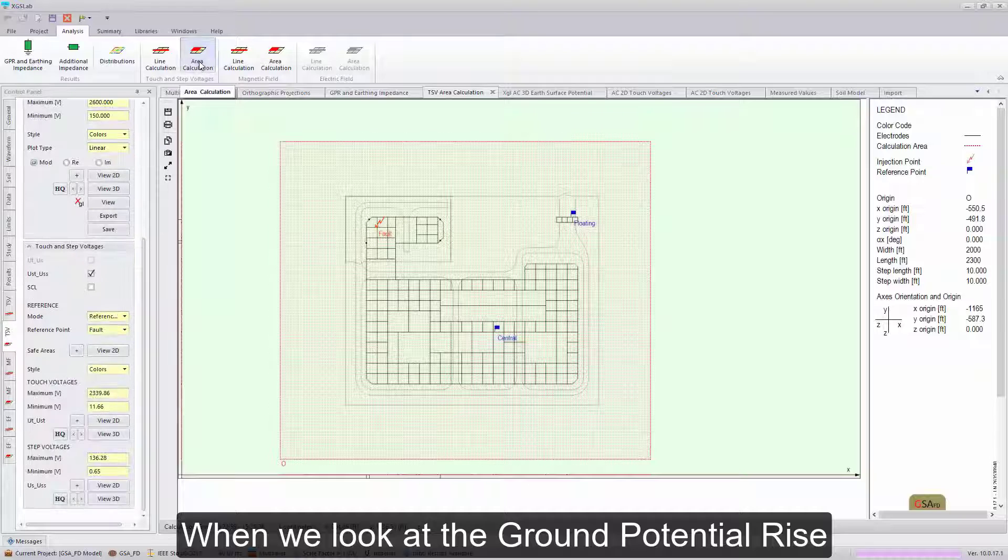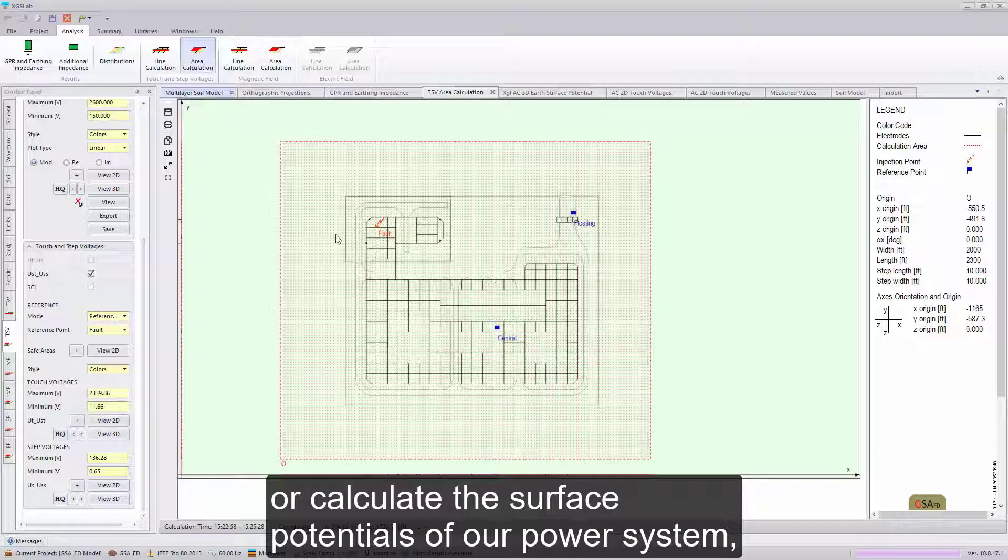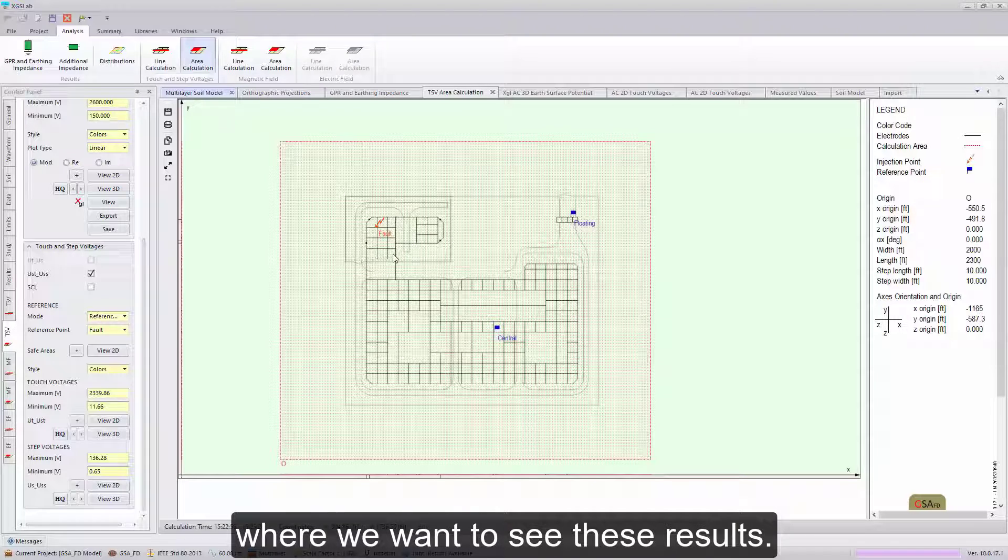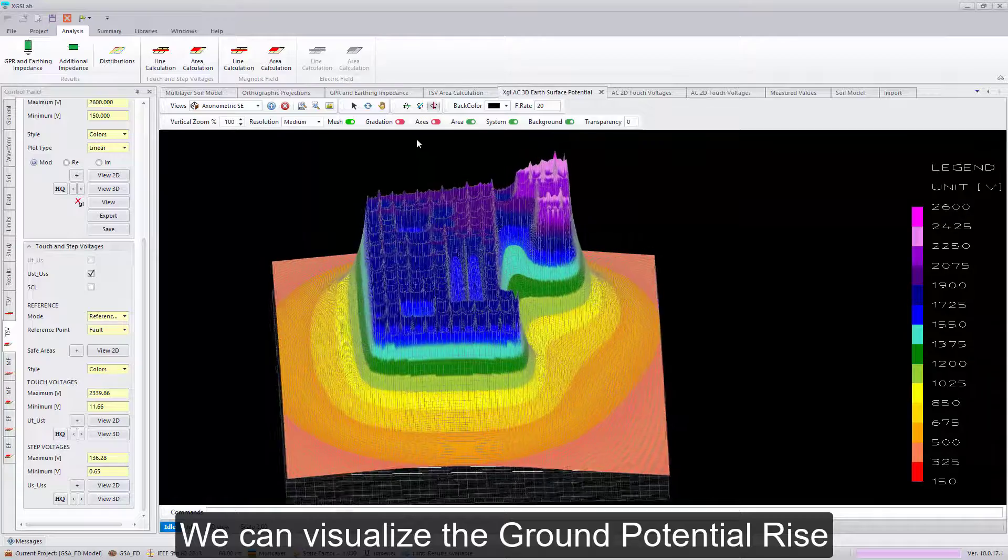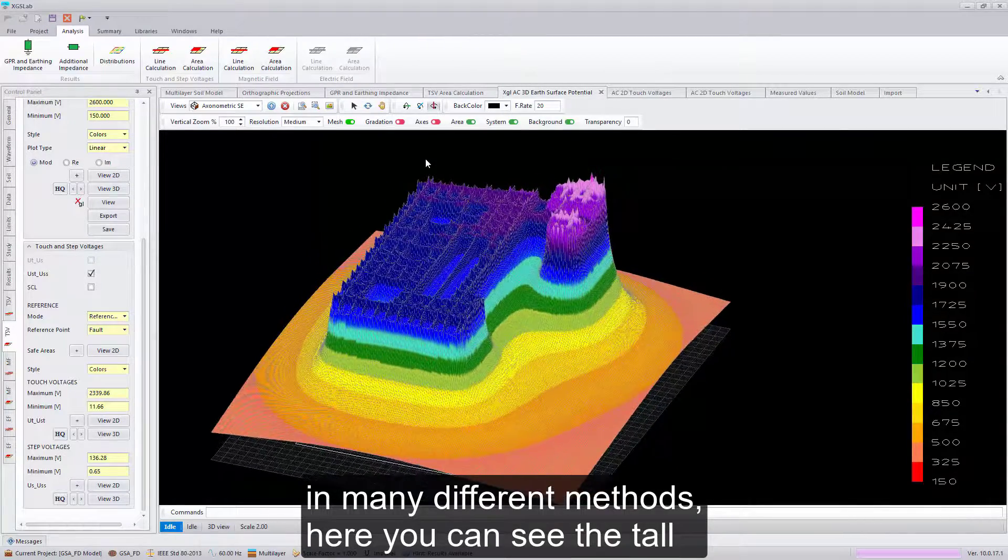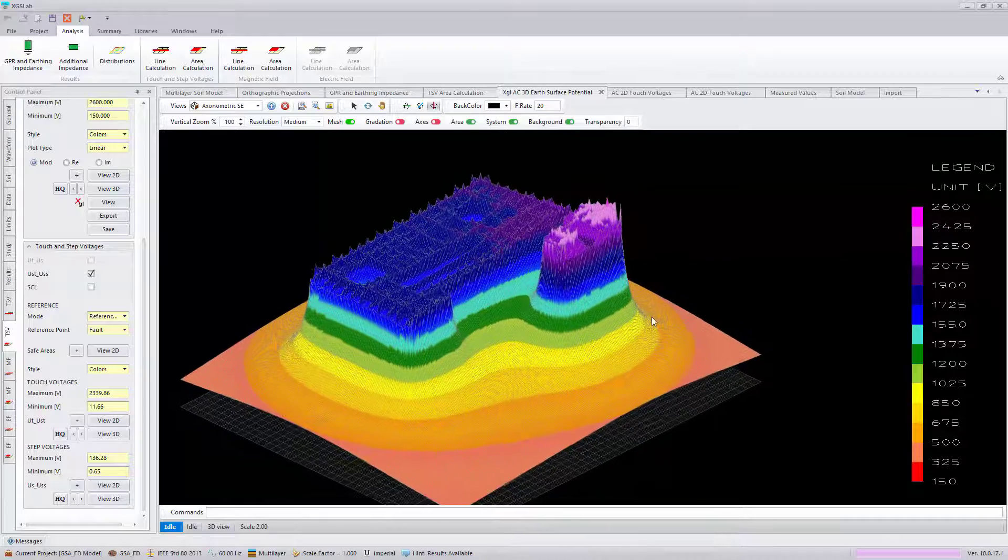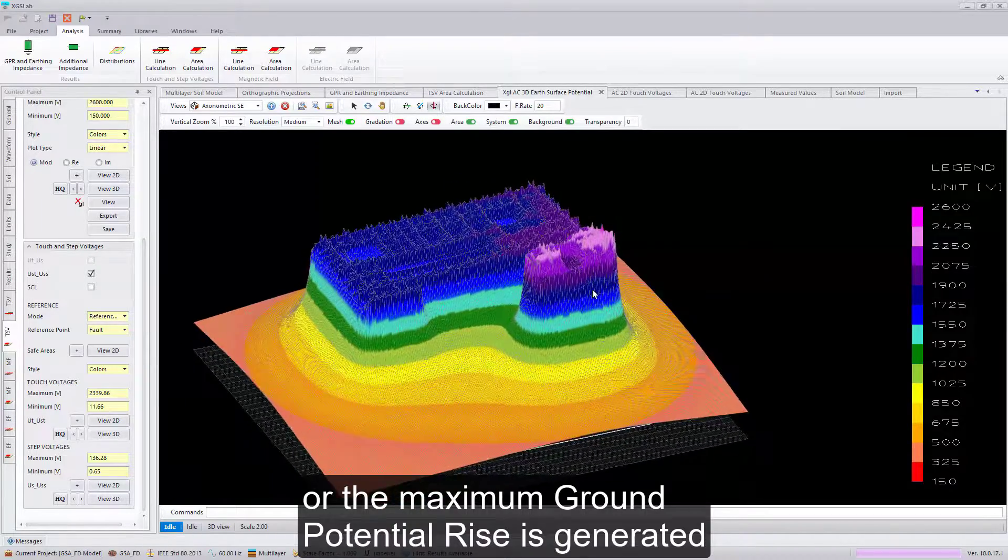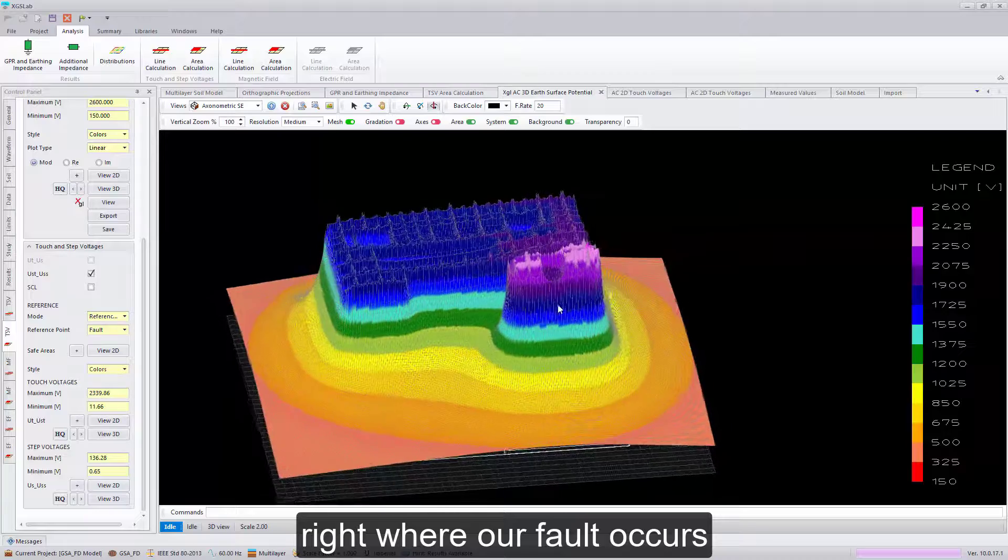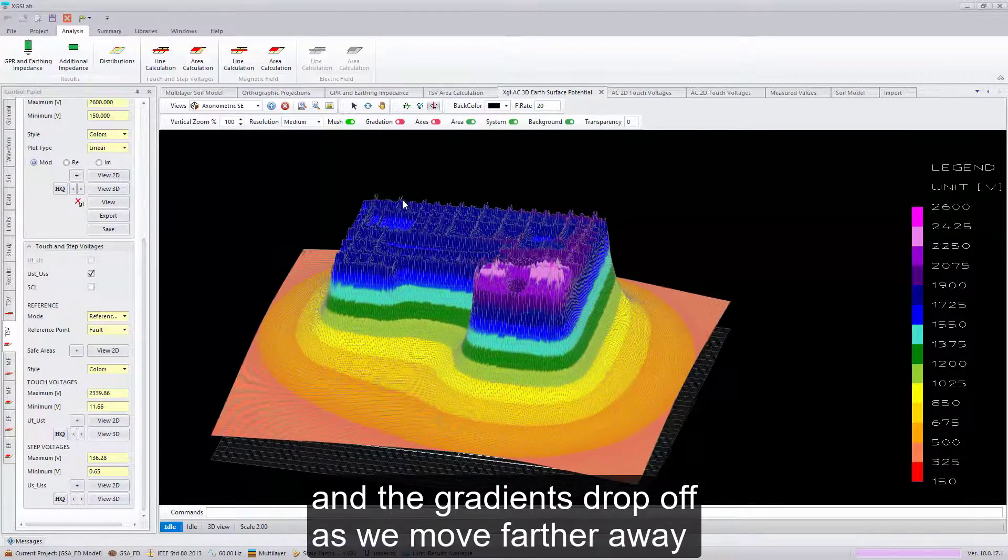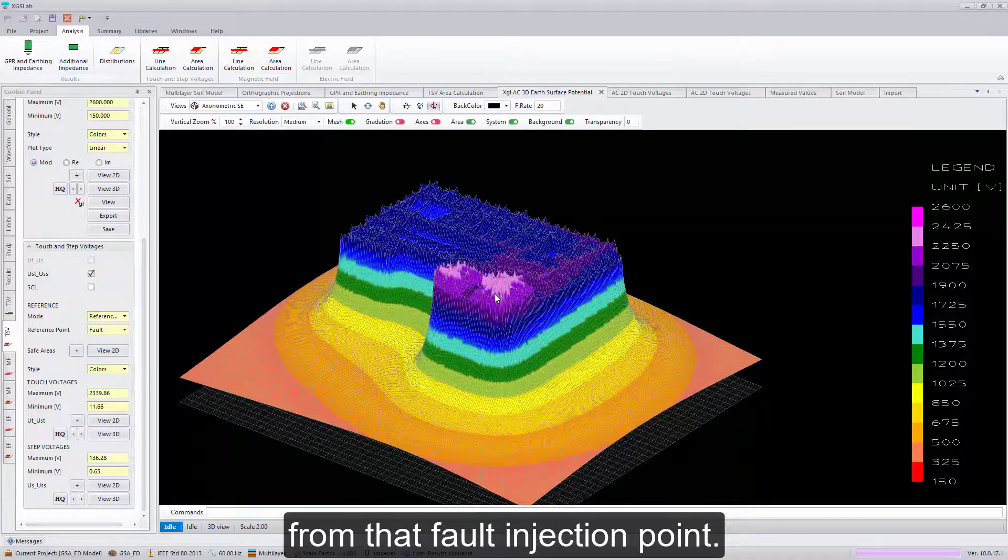When we look at the ground potential rise, or calculate the surface potentials of our power system, we can specify a specific area where we want to see these results. We can visualize the ground potential rise in many different methods. Here you can see the maximum ground potential rise is generated right where our fault occurs, and the gradients drop off as we move farther away from that fault injection point.